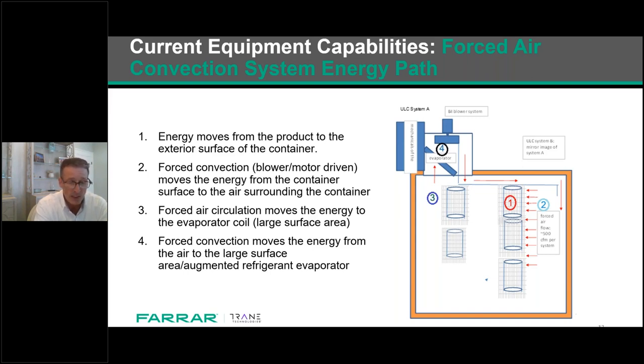Also know that the forced air convection system that's displayed here is 500 CFM per refrigeration system. In this drawing, we only show one refrigeration system, but if both refrigeration systems are operational, it's approximately 1,000 CFM. This is key for the system, especially during pull down to go from plus 20 to minus 80, or during temperature recovery from a door opening, because now we're able to move the energy much quicker because it's convection cooling.